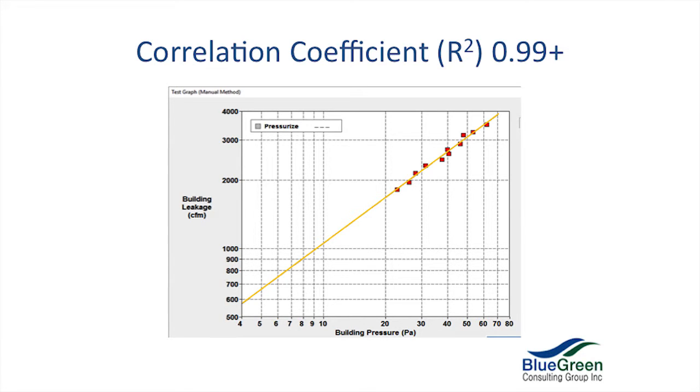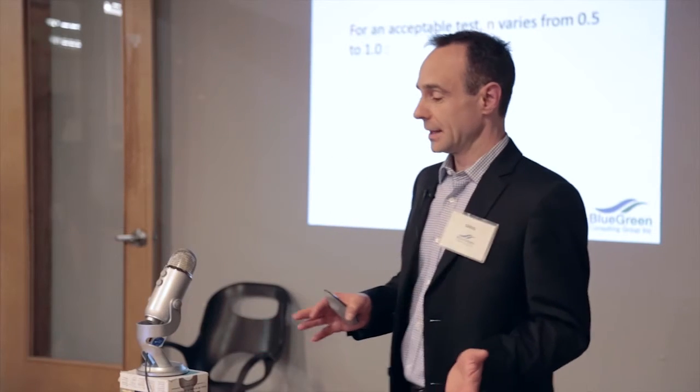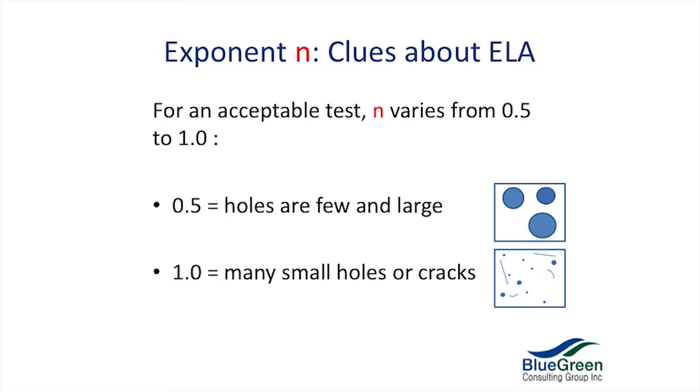Correlation coefficient — the R squared. 0.99 or better for an acceptable test. If it's any less than 0.99, it's not a good test and you have to repeat. That means your data has to fall on that trend line. The exponent n is a great feature of this calculation. N gives you clues about what kind of holes we have in our building envelope — it's a very powerful diagnostic tool.